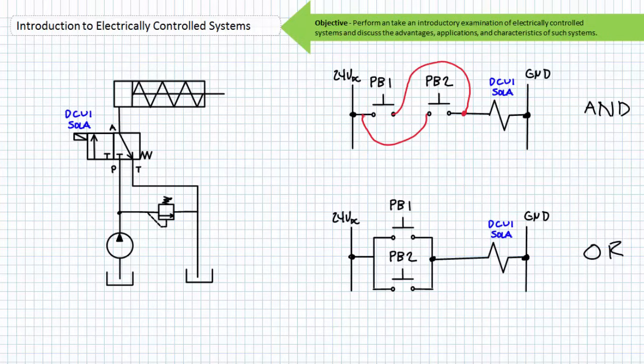As alluded to previously, the PLC is a ruggedized industrial computer that evaluates inputs and issues outputs based on a programmable instruction set. If this electrically controlled system's behavior was governed by a PLC, it would still require two inputs, push button 1 and push button 2, and it would still issue one output to the solenoid. However, the programmable instruction set requires no physical rewiring, but rather a simple reprogramming if the functionality needs to be changed. This is a major advantage.